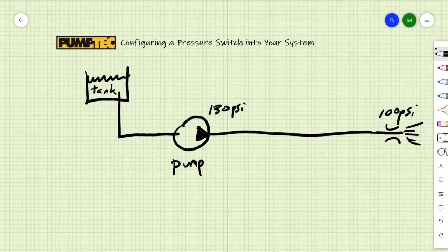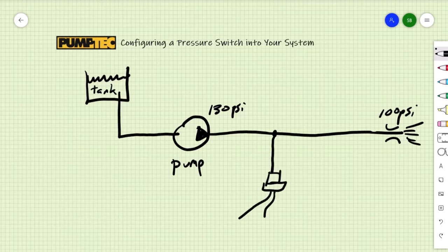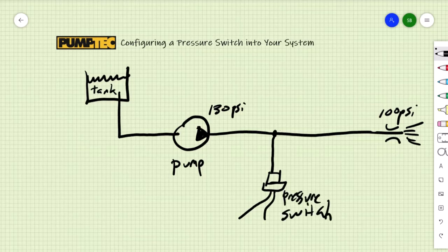Then if you install a pressure switch in the line, which is typically near the pump, you will need the pressure switch to activate at a higher pressure than the pump is seeing. So in this case, something like 150 psi.